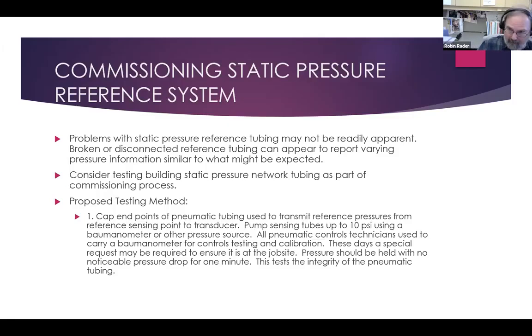Commissioning the static pressure reference system. A building static pressure reference system is a good candidate to be commissioned or checked. You can have problems with your reference tubing that are not readily apparent, such as broken or disconnected reference tubes that will report varying pressure information similar to what might be expected. This can happen at different temperature regimes and things like that. So consider testing the building static pressure network tubing as part of the commissioning process.